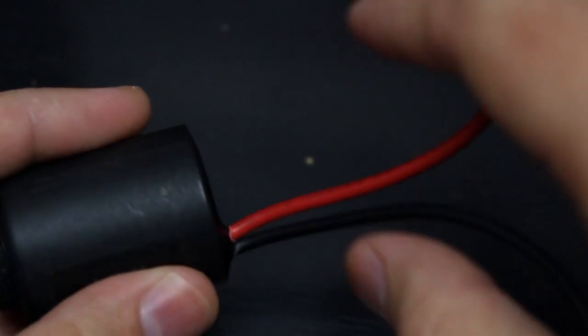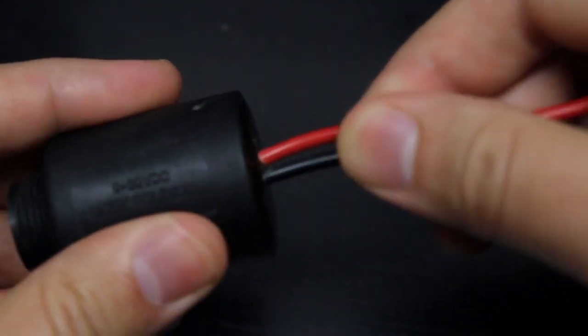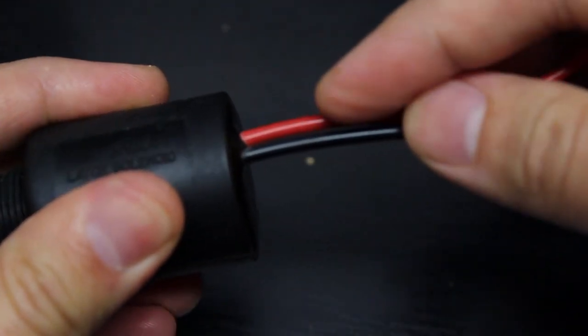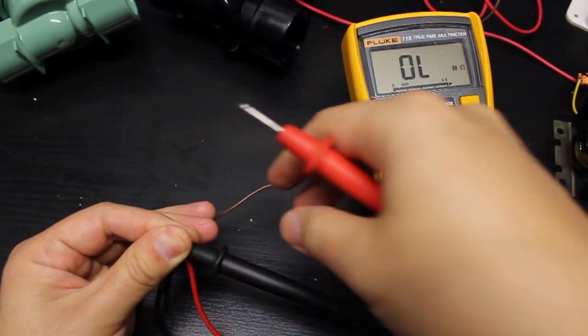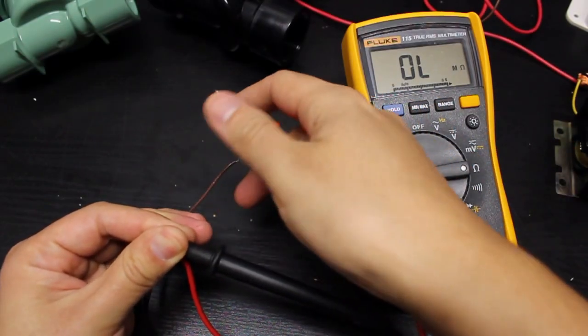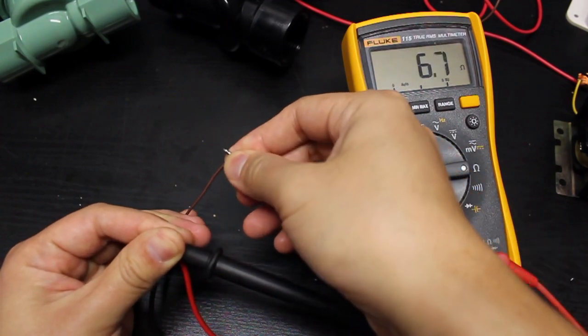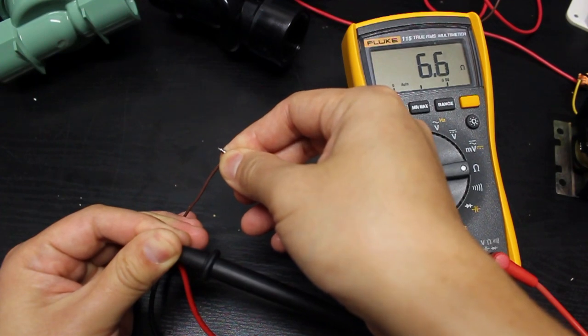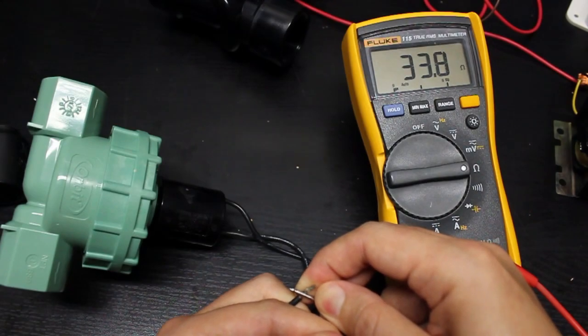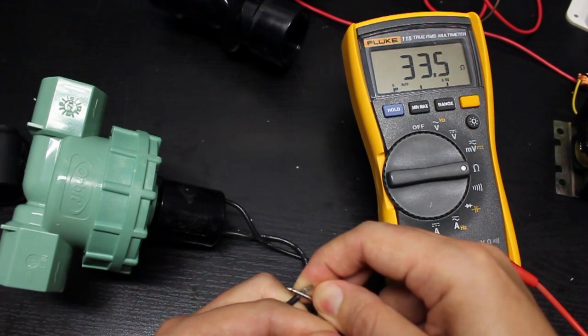These valves also often come with polarized wires of different colors like one red and one black. Finally you can use a multimeter to measure the resistance on the two wires of the solenoid. Latching solenoids usually have very low resistance, well below 10 ohm. In contrast, non-latching solenoid valves typically have a resistance above 20 ohm.